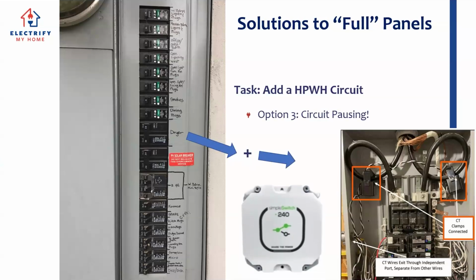Another nifty option is circuit pausing. It works similarly to a circuit splitter, but instead of sharing the circuit, we add two monitors on the main feeds into the panel through this same kind of box. The box constantly monitors the feed, and as soon as total power consumption of the house rolls above 80%, which we saw in the data rarely happens, it shuts off the circuit to, say, the heat pump water heater or range or whatever 240-volt appliance you've added, to ensure the panel stays in the safe zone. We've used this from time to time. It works great for homes that don't want to sacrifice the sharing of two different circuits, and also has space to add these CTs, current transformers, around the mains.